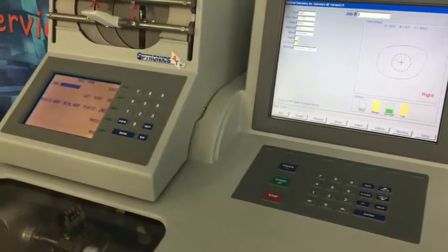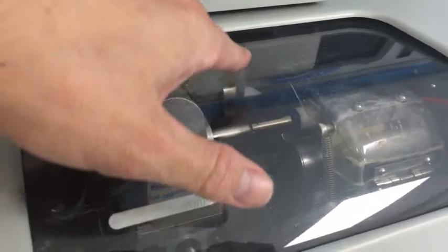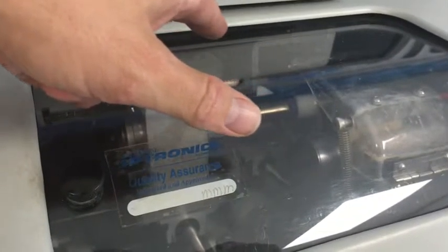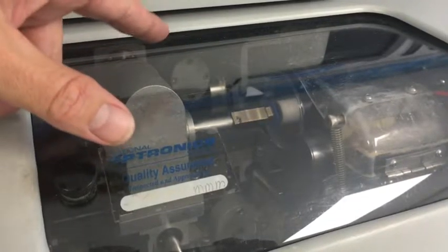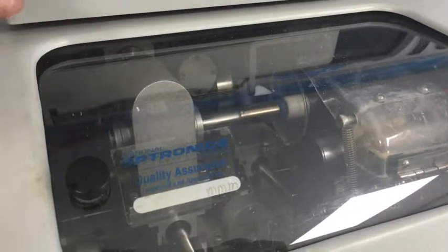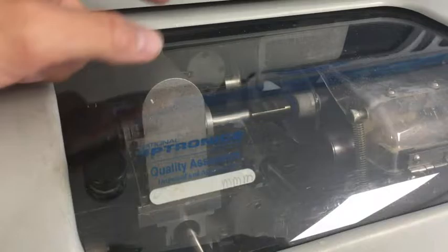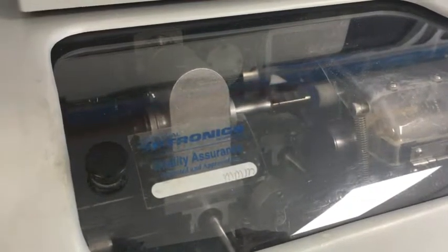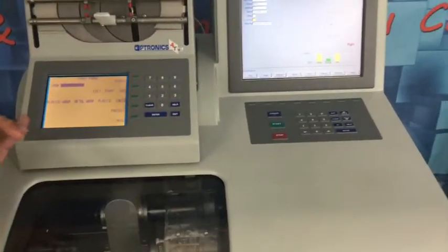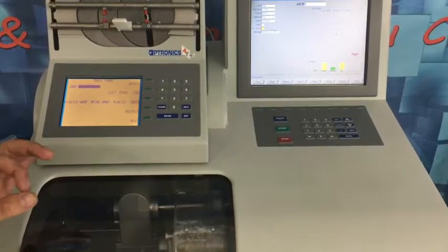Now what it's going to do is it's going to bring it over here. It's kind of hard to see with the window here. It's going to come over here, and touch probes are going to trace the exact frame onto the lens and make sure that there's enough material there to cut the lens out. If it falls off the side of the lens and says that there's not enough material, that usually means either the block was not centered correctly or the lens is not big enough to cut the shape of the frame.